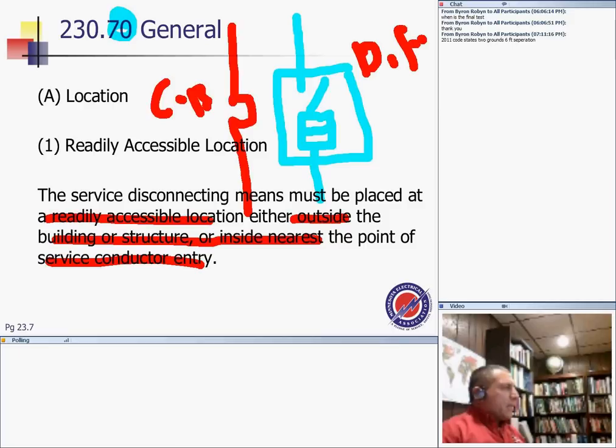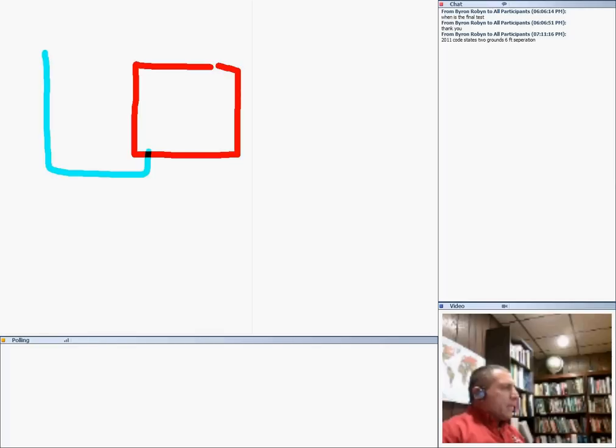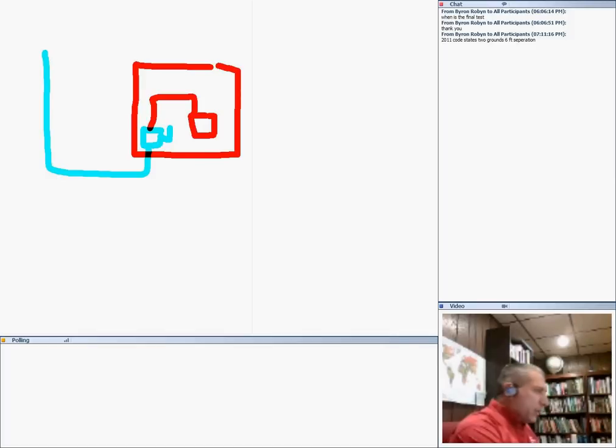That's interesting. As you guys know, here's my building over here. You bring your power lines in from above, or I guess it could be from below, my power lines coming in. The minute that you enter, the closest point disconnect will be located right in here, inside the building or outside the building. Then I can use a feeder inside the building, or a panel and so forth. So you have to have a fused disconnect to protect outside the building or inside the building, as close to the point of entrance as you can.